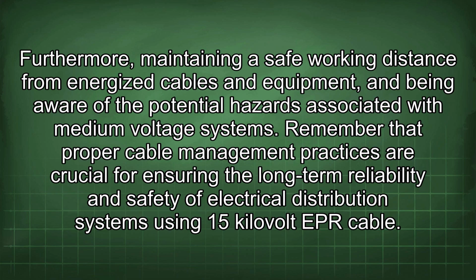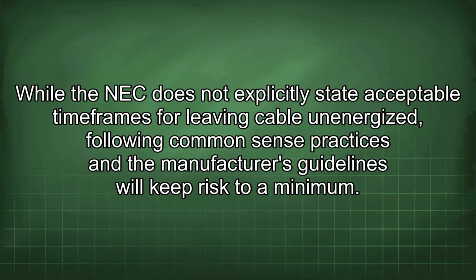Remember that proper cable management practices are crucial for ensuring the long-term reliability and safety of electrical distribution systems using 15 kV EPR cable. While the NEC does not explicitly state acceptable timeframes for leaving cable unenergized, following common sense practices and the manufacturer's guidelines will keep risks to a minimum.